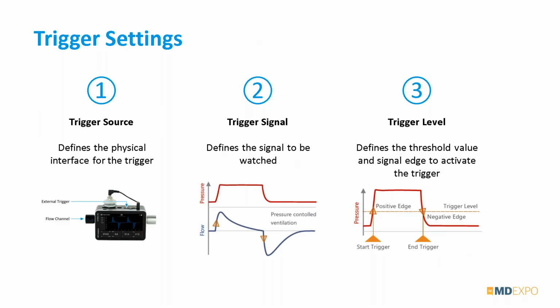And then you need to tell the analyzer, based on the waveform you selected, at what threshold it should interpret a trigger. So I could, for example, say, if my flow rises on a rising edge and crosses the 3 liters line, then this is a sign of the start of an inspiration. If it crosses a certain value on a falling edge of the signal, then this is my trigger for the end of the inspiration phase. And then the next trigger starts the next inspiration phase. Does that make sense so far?